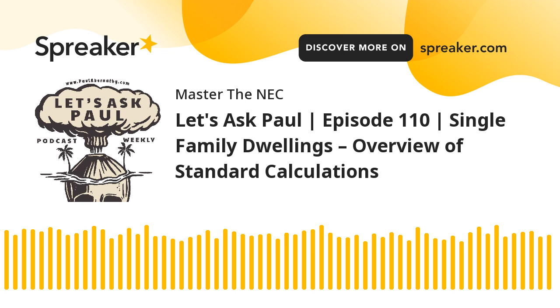The reason for that is because we already have rules that we're going to apply to those. So you don't want to double dip there. It only applies to those appliances that are fastened in place, and it only applies when they're a quarter horsepower or greater, or 500 watts or greater, whatever the load is, and they're fastened in place, okay? And you have to have what? 4 or more. If you have less than 4, then you're just going to take them at the nameplate value, and we all know how you get VA from that, right? You take whatever the value is in amps on the nameplate, multiply it by the voltage, and that's going to give you your VA. And you're just going to add that as a contribution to your calculation, okay?